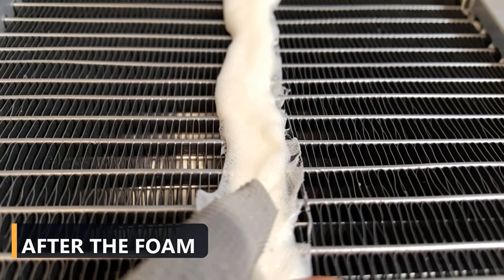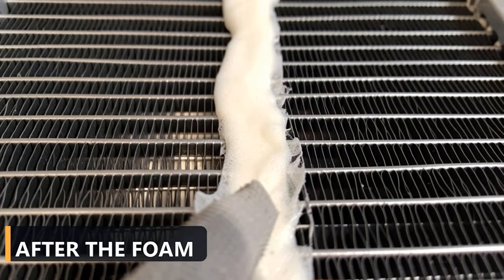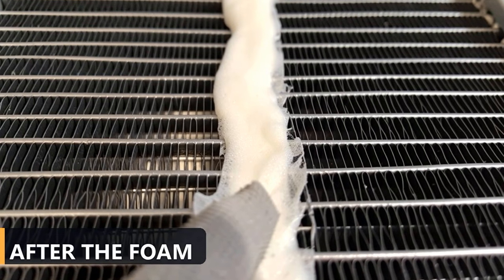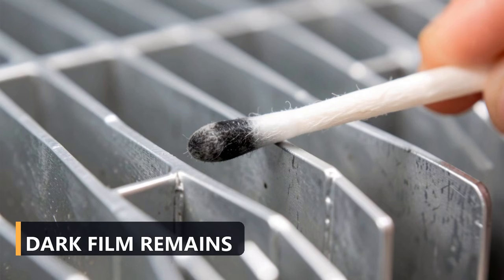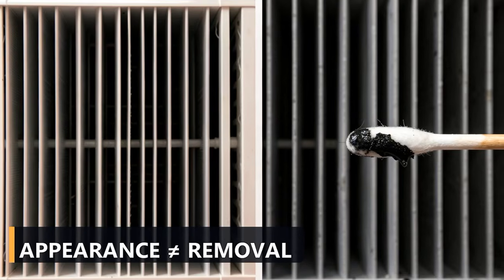The metal looks brighter, but a cotton swab still collects a dark film from between the fins. That is the first secret. A chemical reaction can change the appearance of contamination before the contamination has actually been removed.